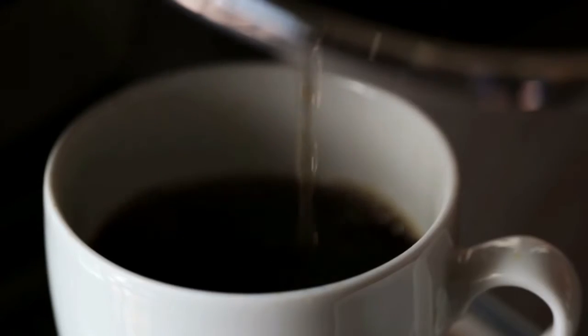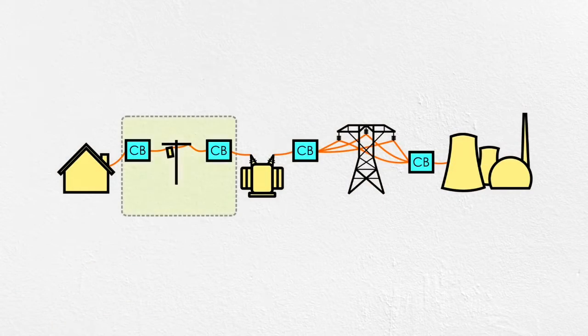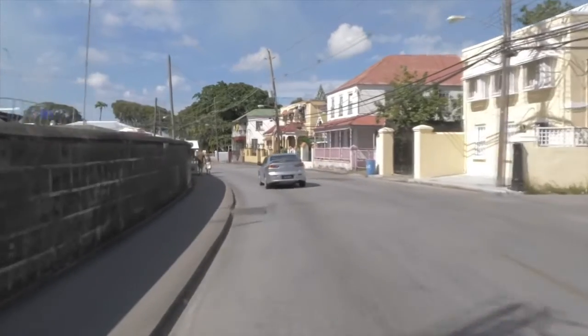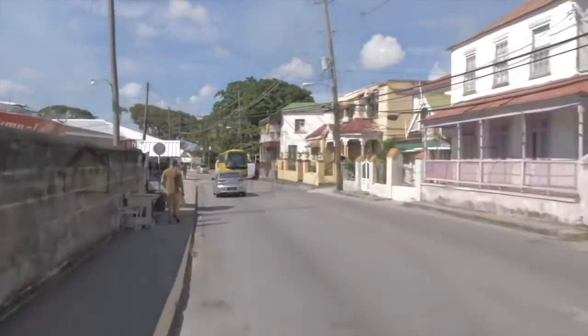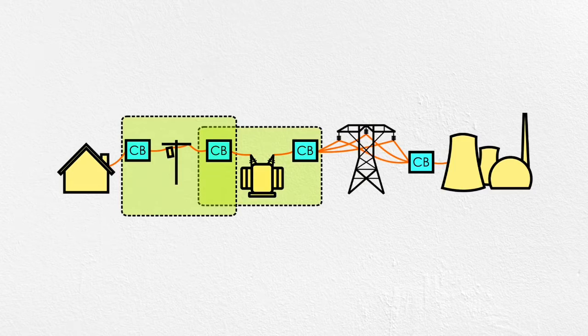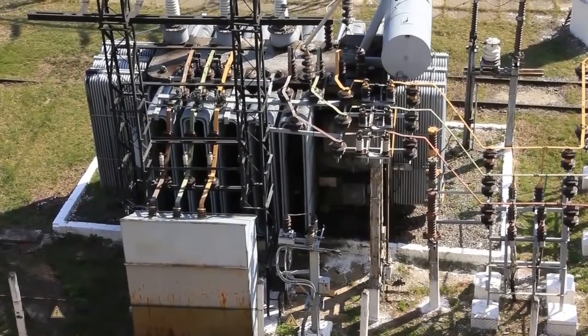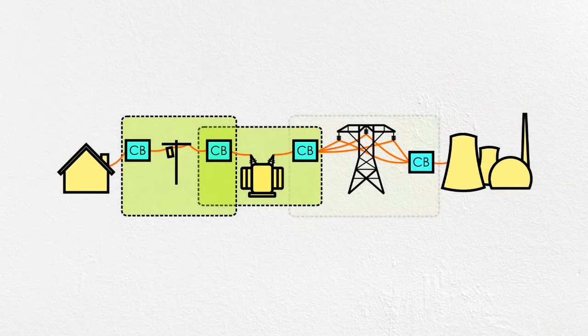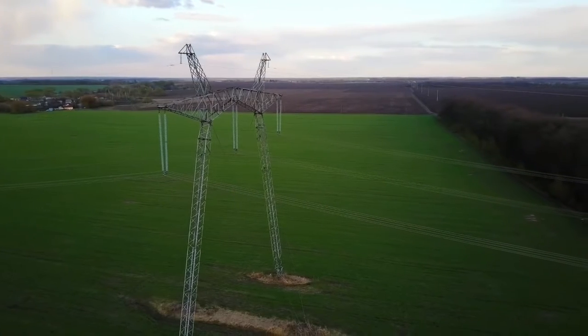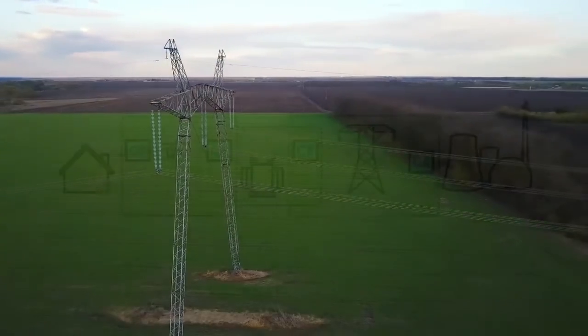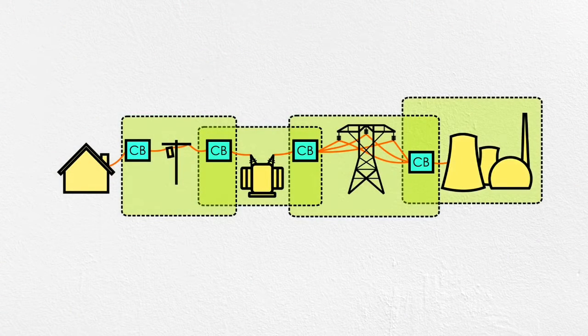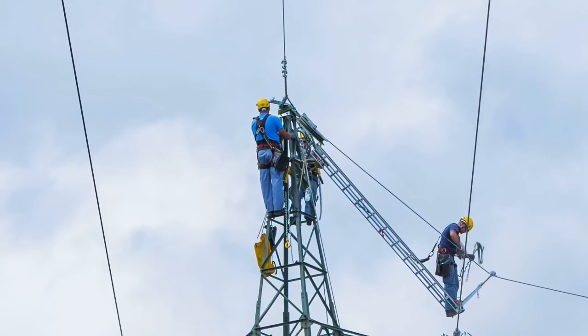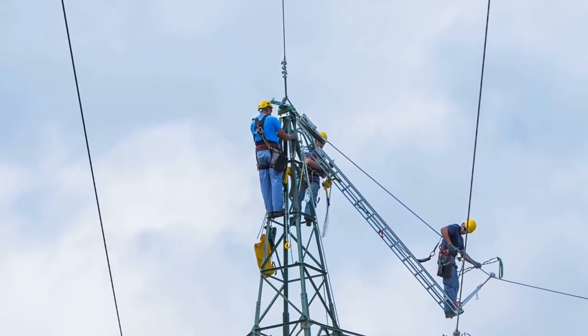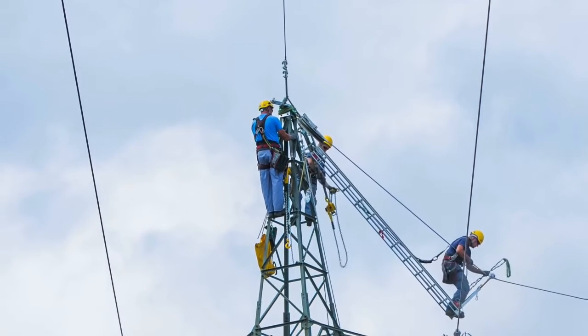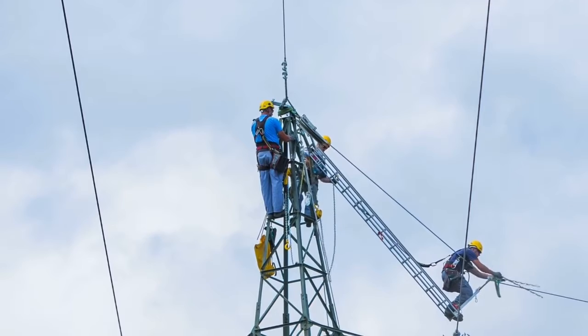You can trace these zones of protection from your house all the way to the power plant. A short circuit in your coffee maker isn't going to overload the service transformer because there's a fuse or breaker in between. If a car knocks down a pole and grounds out a line, that's not going to take out the entire substation, again because it's isolated with a fuse or breaker. If a transformer has a fault in a substation, it's not going to melt the transmission lines feeding it because it can be isolated using breakers. And if a transmission line sags into a tree limb, the resulting surge in current is not going to destroy the generator at the power plant because it has its own zone of protection. Of course, this is a super simplified explanation. These zones of protection are thoughtfully considered to balance the complexity and resiliency of the grid. But how do they actually work? There are a wide variety of types of electrical faults.